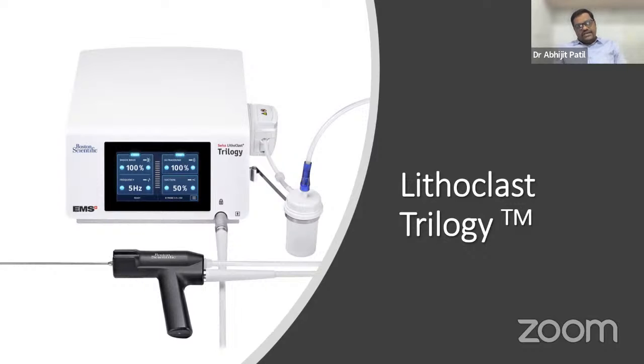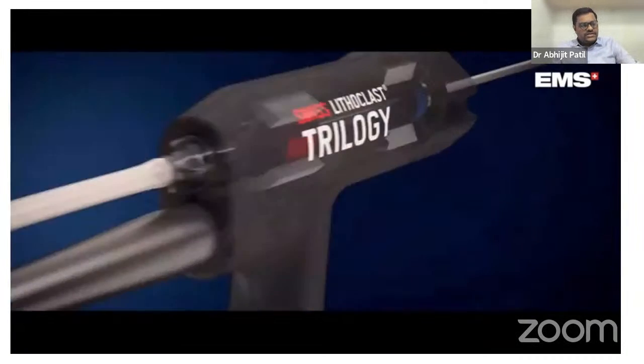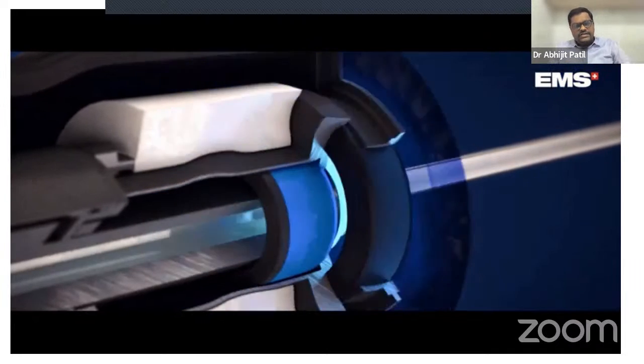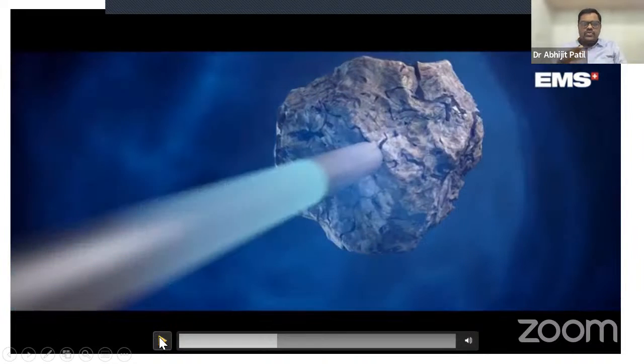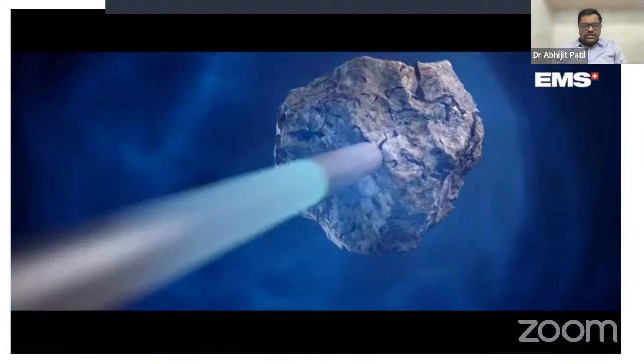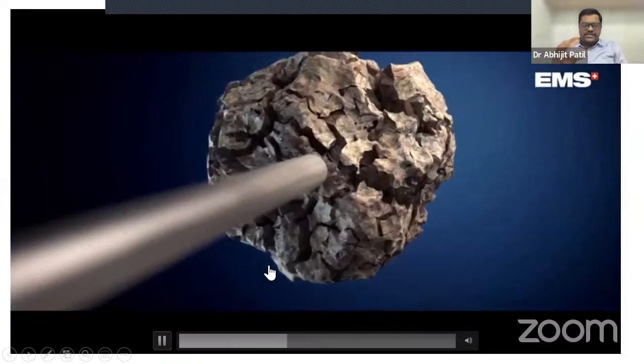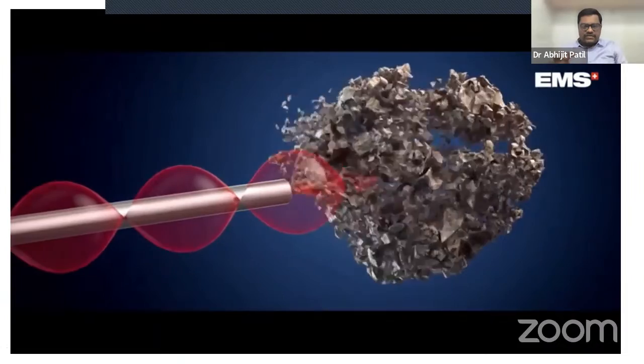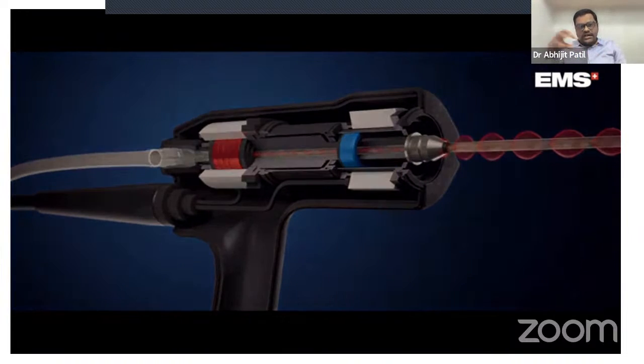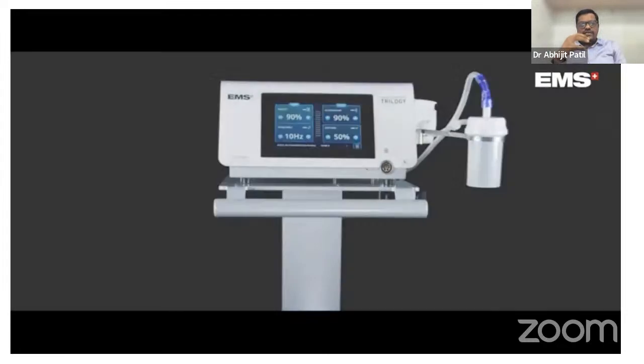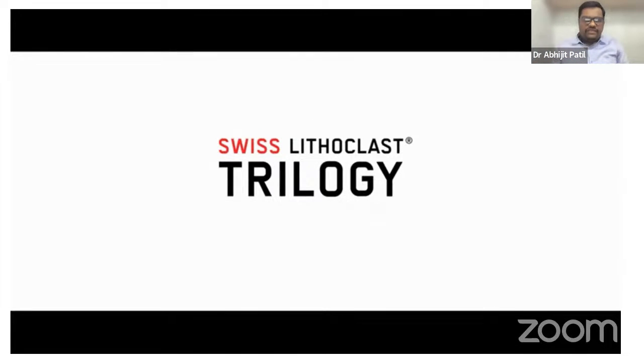Now coming on to the next device, which is the Boston Scientific or EMS Lithoclast Trilogy. So it has three components. It has a ballistic component, it has an ultrasound component, and it has a suction attached to it. Now, this is the probe where you can see this probe itself moves back and forth. So this is the ballistic component which breaks the stones into larger fragments, and the ultrasonic component breaks it into finer fragments and it sucks out. So these three energy sources, or the three components of Trilogy, work in harmony to clear the stone very fast.